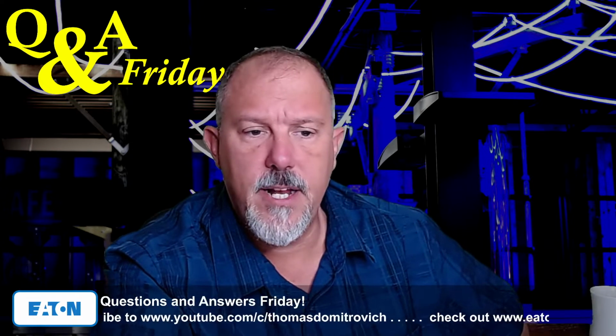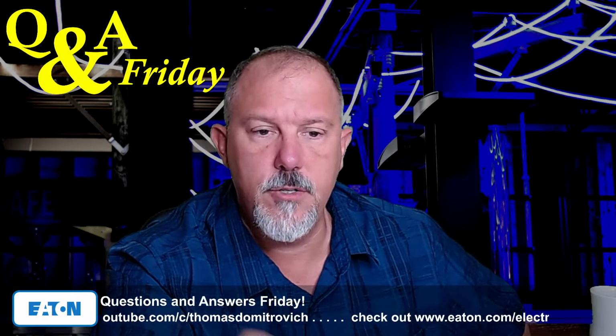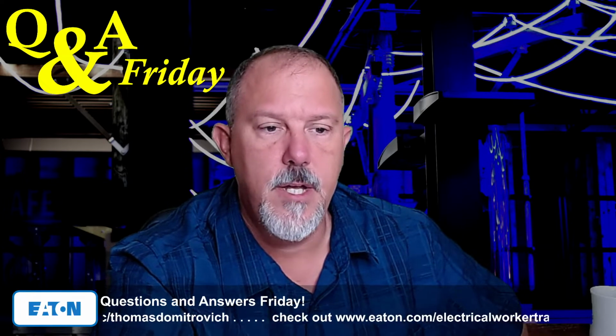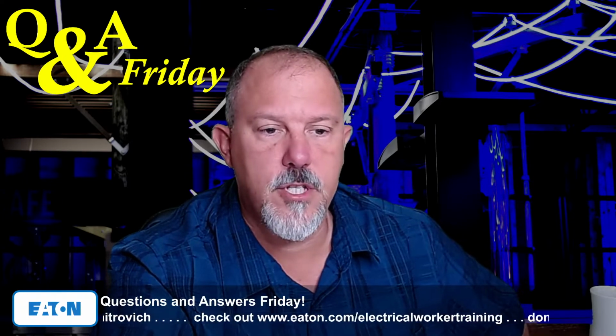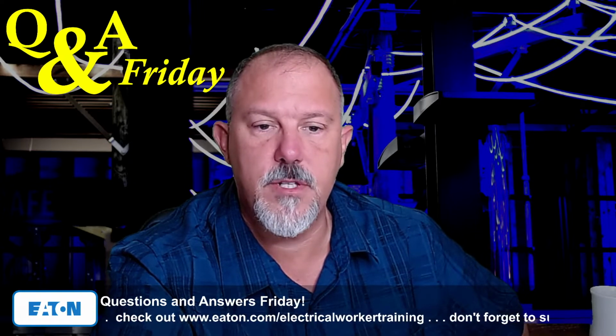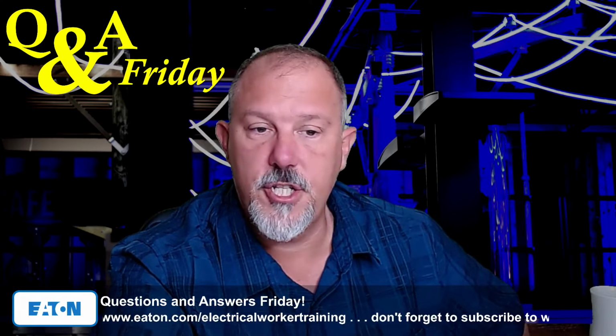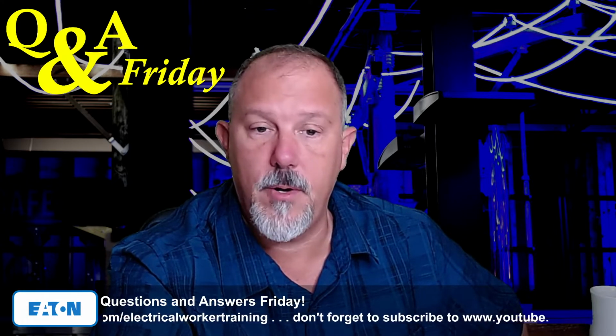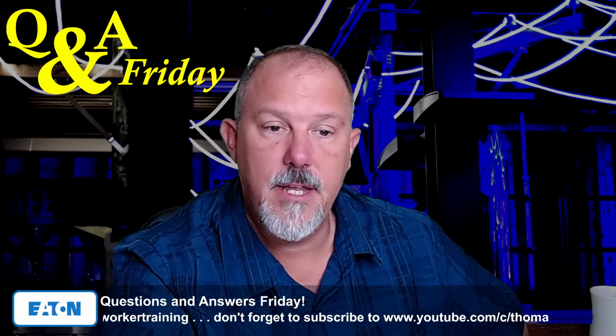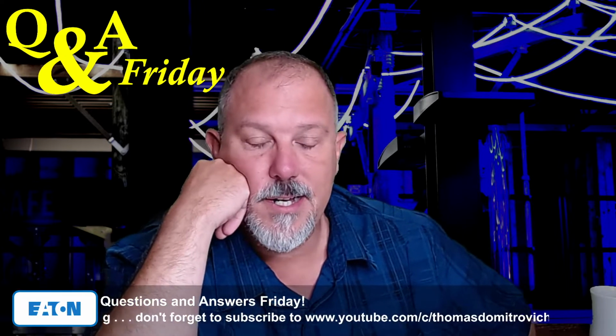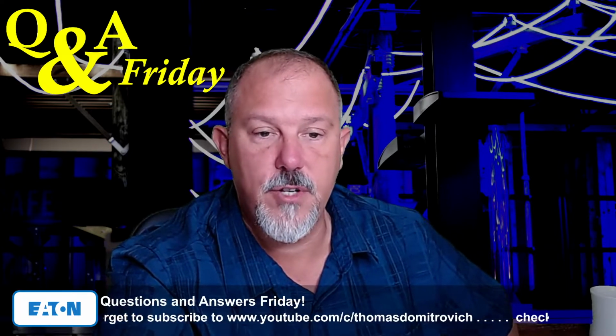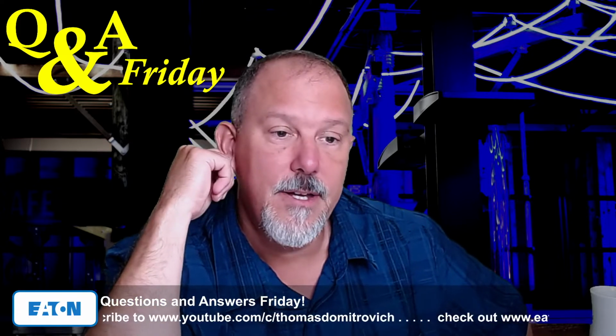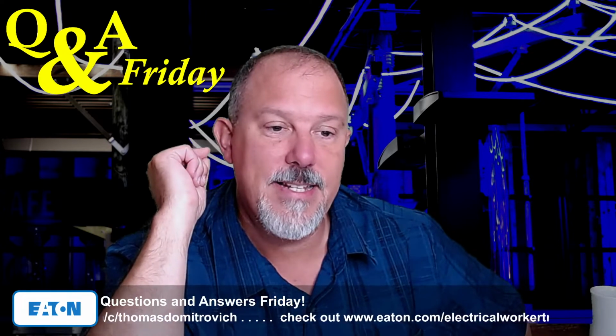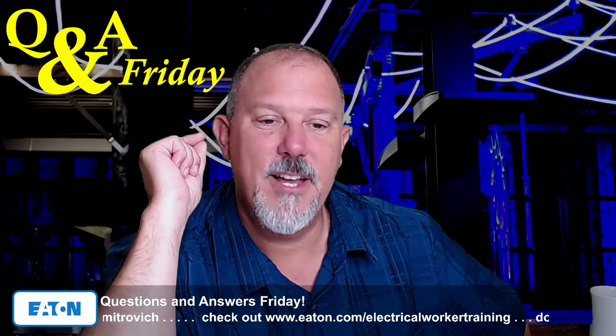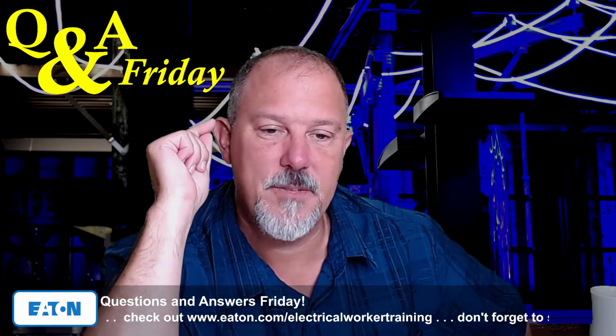So 250.94, you say many grounding studies conclude to prohibit things like metallic shields of fiber. As a result, the serving internet utility is required to serve the premises with a non-metallic means. We have no metallic shield in the fiber, thus no need to interbond. Yet one would be required to add this thing that forever tempts people to use it. NEC grounding and bonding rules for station service transformer conflict with the NESC, yeah. Yep. The backfeed power warning labels required by Article 490 will require one to pepper a station with backfeed power warning labels that would be so prevalent as to be ignored.